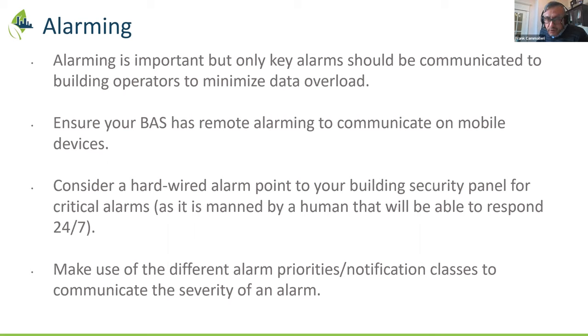Again, this would only be for critical alarms, maybe one or two, like a space temperature sensor in a critical place, or your boiler loop if it's in really bad shape. You want those routed so people can respond quickly, especially when it's extremely cold out.